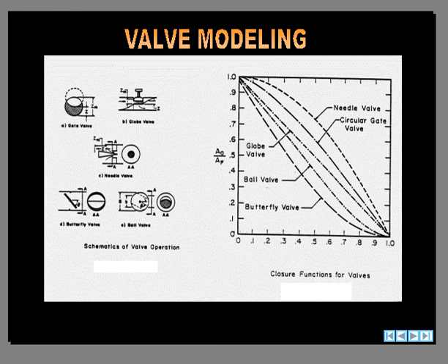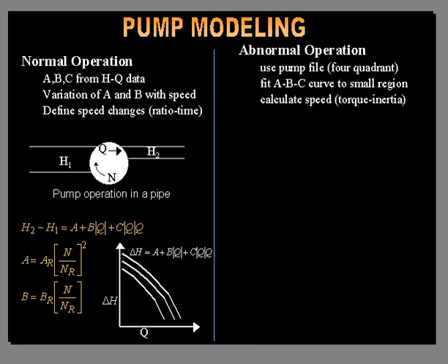Pumps, you can model pumps two ways. We can use just a standard ABC characteristic. This works only for normal operation. If we have a pump trip where the pump can turbine and the flow can reverse, we have to use these Suter diagrams, which are dynamic characteristics over an entire range of possible.